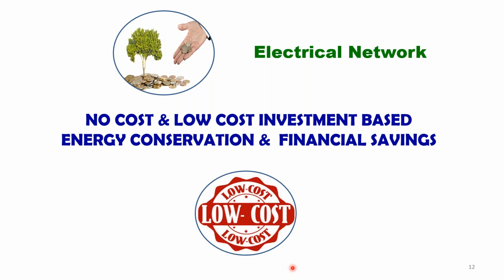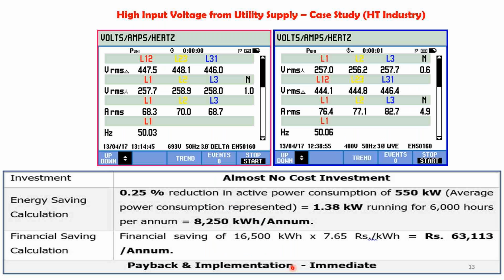We tried some of the proposals and we got some results, and those results are presented here. The first point is that this is an industry where we have a measurement of the input system. The input voltage is going to be very high. The line-to-line voltage is 447, and it is measured even in the daytime, around 1 p.m. So even in the daytime itself, the line-to-line voltage is very high, where the line-to-neutral voltage is almost 255 to 260. During the night time, the voltage is still higher. So we got a record of 456 line-to-line voltage and line-to-neutral voltage of 265, which is a very huge voltage.